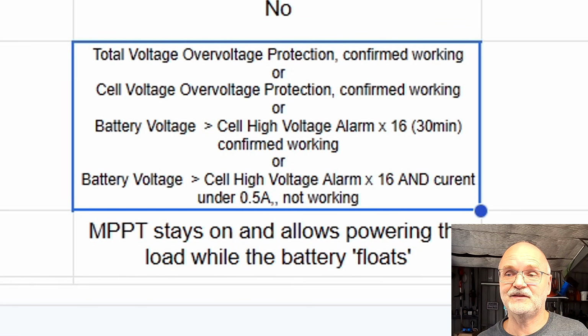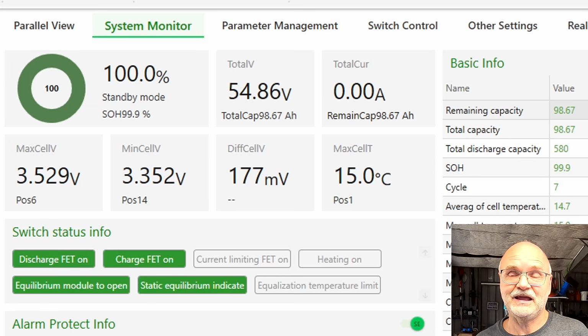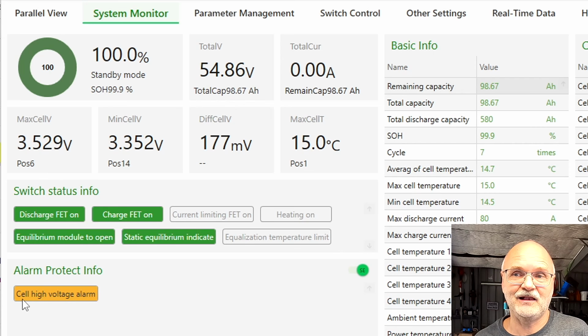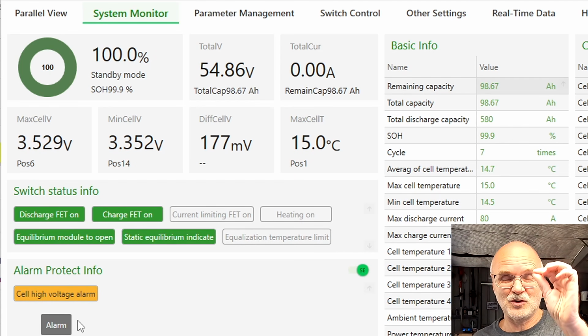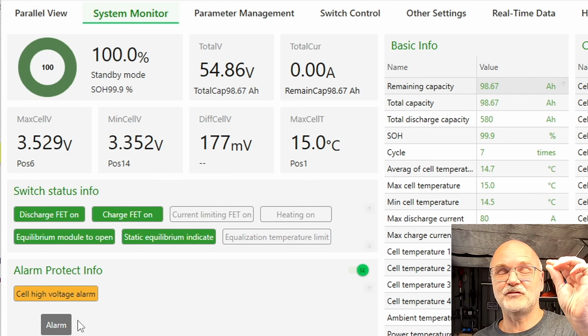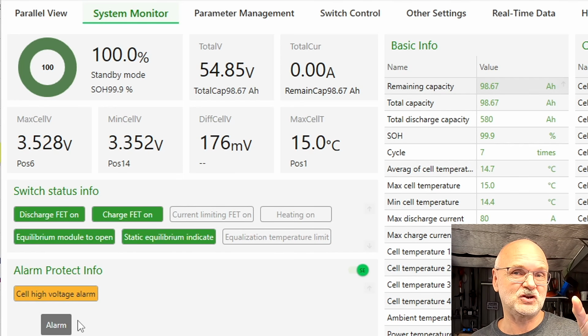So it's the high voltage alarm times 16, and our battery voltage needs to be higher than this setting for 30 minutes. This also resets our BMS to 100%. As we can see here, we are under 55.2 volts, which is our set voltage to charge the battery to, but we have a cell high voltage alarm triggered. So you set this alarm accordingly to when you want to trigger this 100% state of charge reset. This is actually good and not so good.